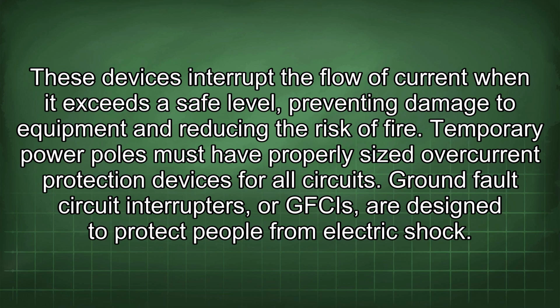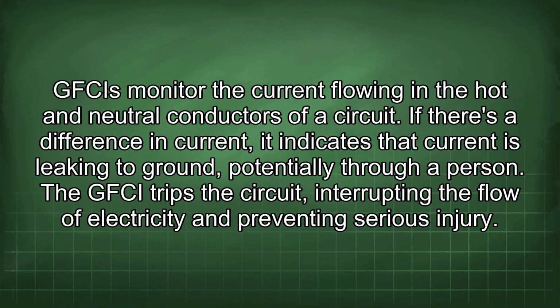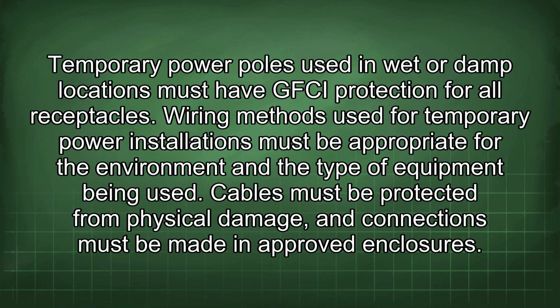Ground fault circuit interrupters, or GFCIs, are designed to protect people from electric shock. GFCIs monitor the current flowing in the hot and neutral conductors of a circuit. If there's a difference in current, it indicates that current is leaking to ground, potentially through a person. The GFCI trips the circuit, interrupting the flow of electricity and preventing serious injury. Temporary power poles used in wet or damp locations must have GFCI protection for all receptacles.